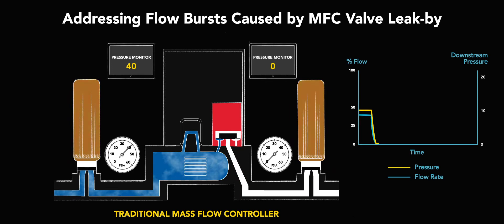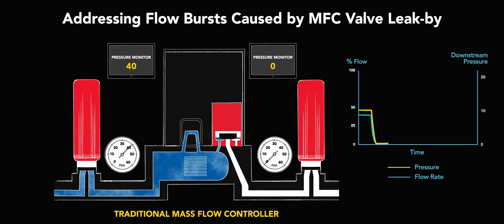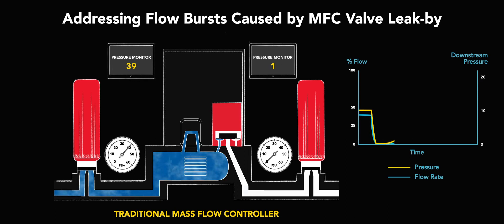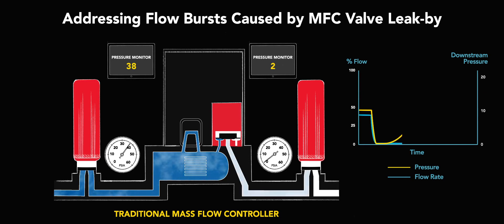Traditional MFC control valves are typically only rated to close down to less than one percent of full scale. The MFC and pneumatic isolation valves are now all closed. The process recipe is now complete, and gas will not flow to the process chamber.